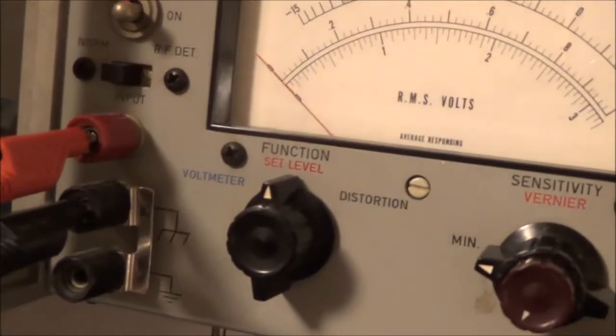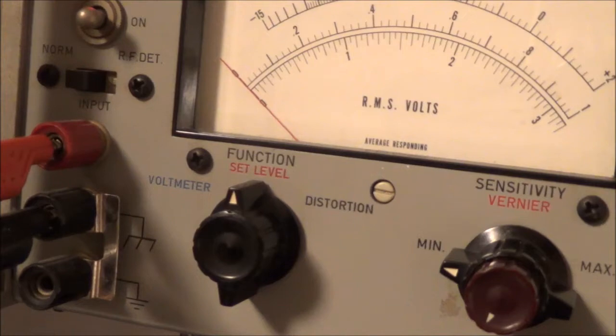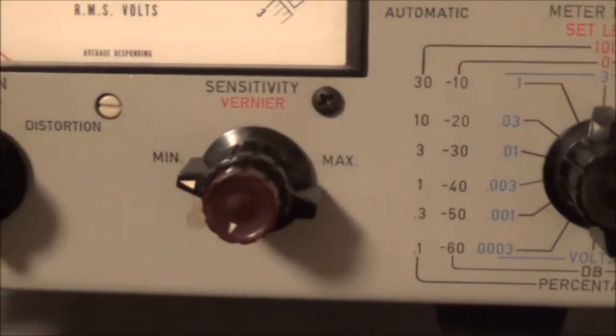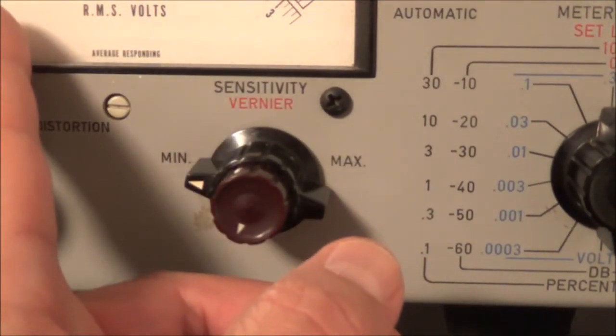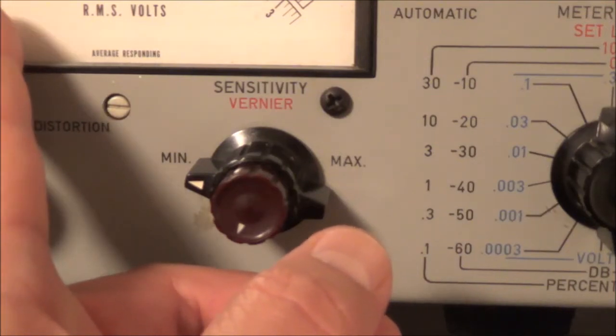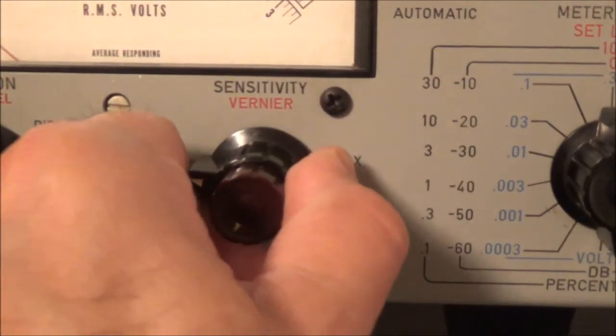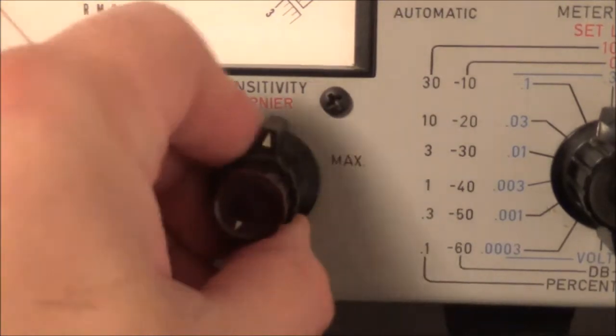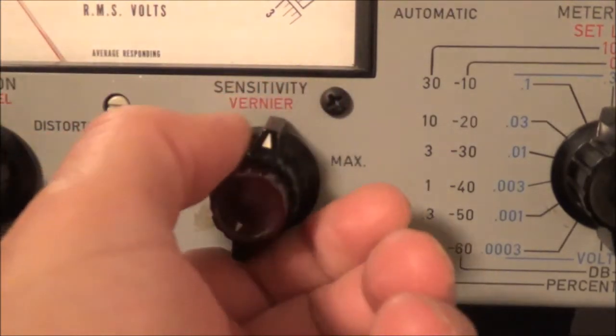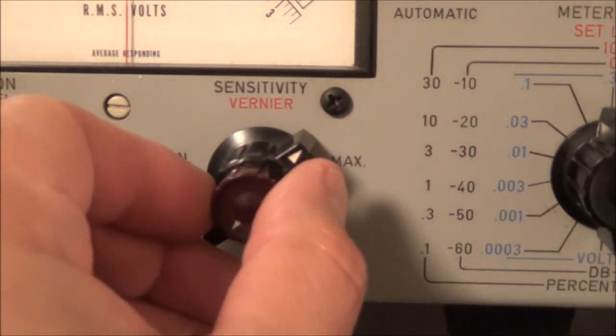Of course, I'm already hooked up. Normally the manual says to do the hookup now. I don't think it makes any difference. And we use the sensitivity switch here. We want to get a reading where the needle deflects at least over one third of the way. That's not one third. Okay, right there. So we did that.